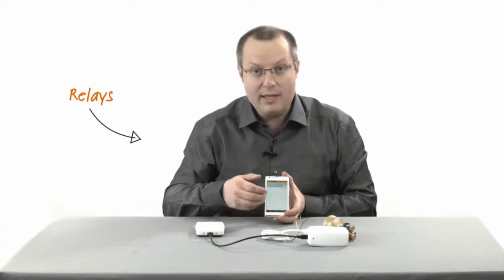Programming of binary input, programming of relays, and a lot of other settings like some error settings. Speaking about errors, you also get access to the last errors the actuator has met, and the possibility to read some statistics of use, like the total motor usage time and the cumulative distance it has covered.